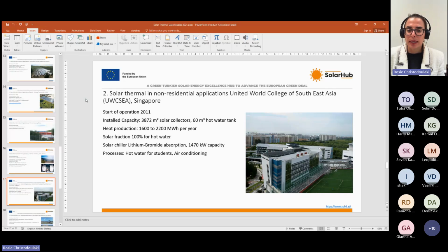And not only this, it can also produce cooling energy, and with a lithium bromide absorption chiller of a capacity of 1.5 megawatt, it can also cover the air conditioning needs of this building. So this solar thermal system is used for two processes: the hot water for the students' campus, and the air conditioning of the building.